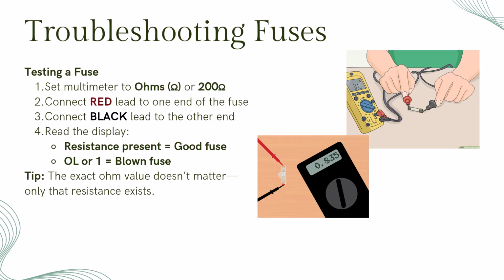Testing a fuse uses the same method as testing a DC solenoid. Set your meter to ohms, connect one lead to each end, and check the display. If you see any resistance, the fuse is good. If it shows OL or 1, that fuse is blown and must be replaced. The actual number of ohms isn't important. It's the presence or absence of continuity that tells the story.